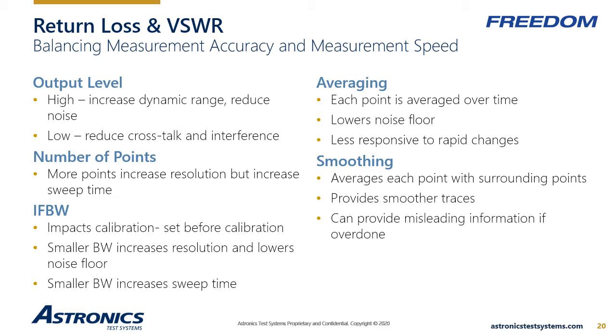The IF bandwidth should be set before sweeping, as any changes will require the VNA to be recalibrated. By decreasing the bandwidth, less noise is captured in the signal measurement, which lowers the noise floor. The added resolution will make it possible to better distinguish between adjacent sweep points that might otherwise blend together. However, this increased resolution also comes with a cost of increased sweep time.